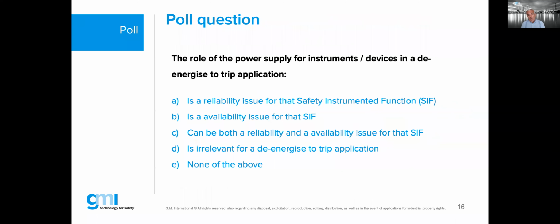And the role of the power supply, and I'm talking about the power supply itself to feed your instruments. So think about the field power supply for your instruments and for your devices in a de-energized to trip. I've got a few questions here. The first question is the poll question that you are allowed to try to answer. The first answer is A: the power supply plays a reliability issue for that safety instrumented function. That is answer number A.